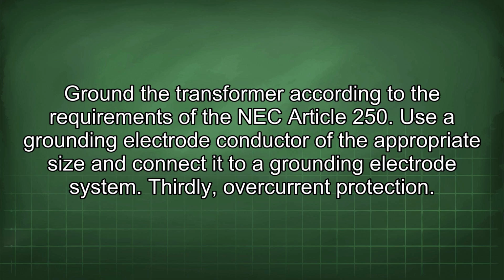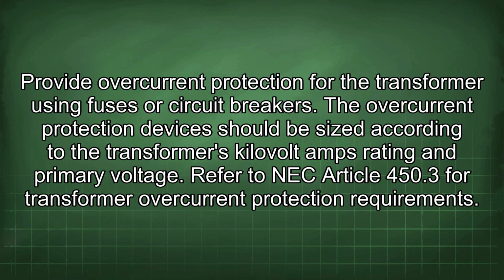Thirdly, overcurrent protection. Provide overcurrent protection for the transformer using fuses or circuit breakers. The overcurrent protection devices should be sized according to a transformer's kilovolt amps rating and primary voltage. Refer to NEC Article 450.3 for transformer overcurrent protection requirements.